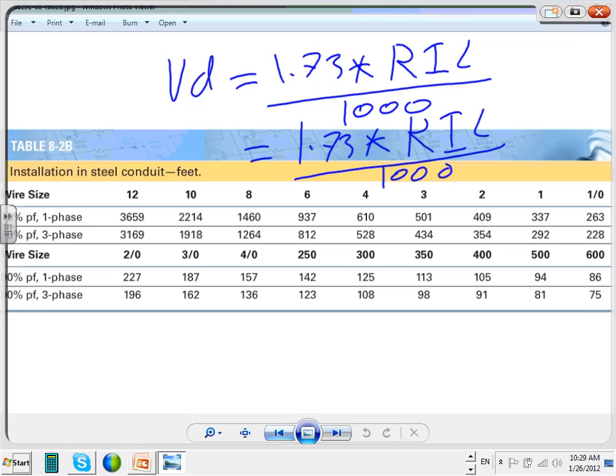This is just FYI. If you guys go to page 1-23, this is commonly used practice. Go to 1-23, please. The table does this calculation for you, okay? If you look at the top, it says wire length versus size, maximum voltage drop. So maximum wire length at 240 single phase, 2% maximum voltage drop. We use this as a guide, already calculated for you, for voltage drop. Can you guys see that? Page 1-24.